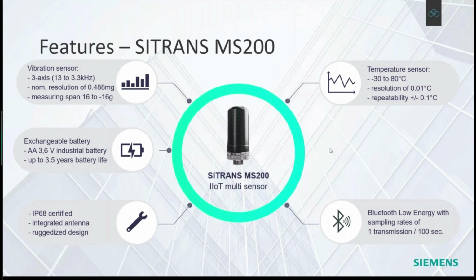It runs and reports back once every 100 seconds. So that's one burst transmission per 100 seconds, and that gives it a long battery life as well. There are certain applications where you won't use it - if it's cyclic every second, it won't tell you anything sensible. So we're looking at sustained vibration or displacement in a belt or housing over time. That's the MS package, the transducer itself.